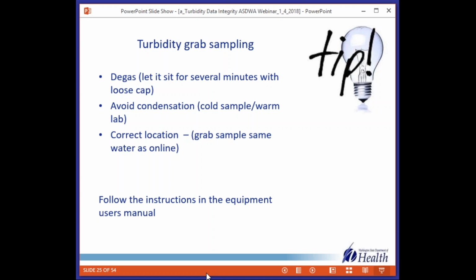Avoid condensation. Remember that the benchtop units are shining light, and they're going through glass and water. So there's two interfaces there. If you have condensation, you're essentially adding another place where light can be diffracted. The online instruments don't have that extra glass step. A little bit of silicone oil can be quite useful in reducing the condensation.